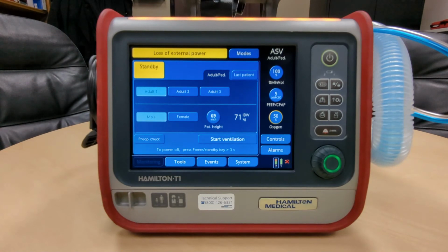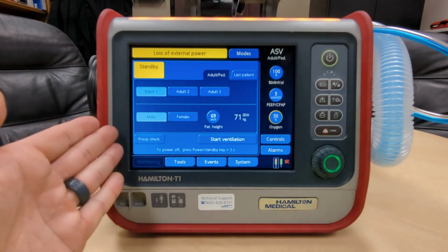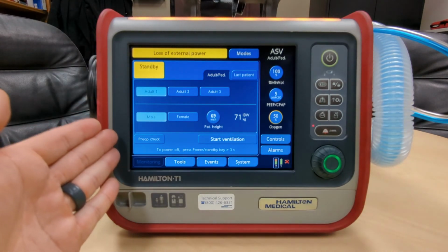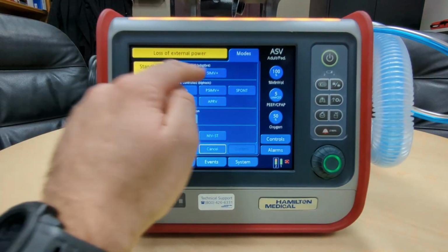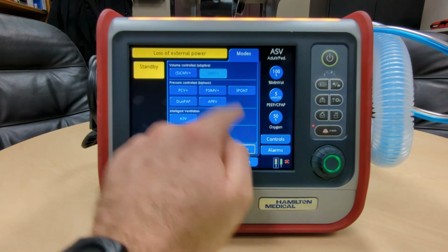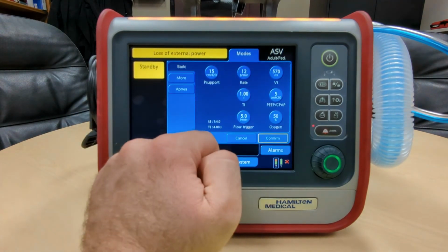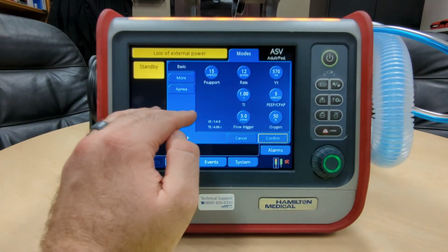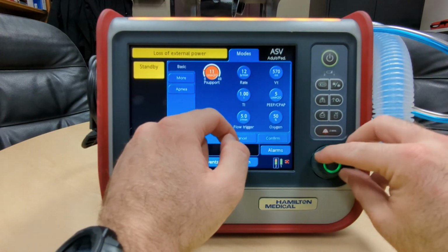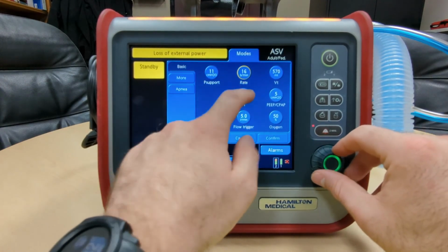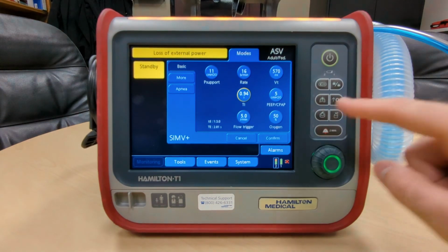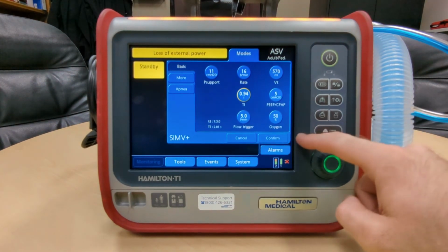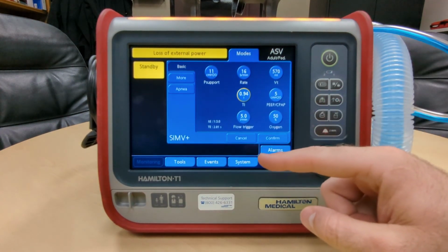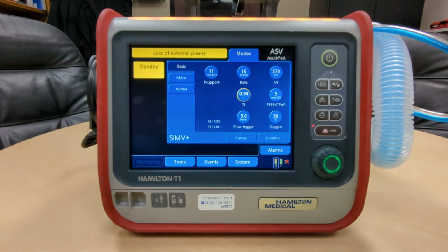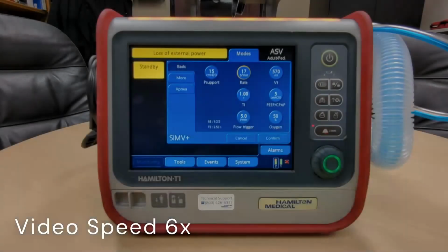One caveat worth mentioning is, when the ventilator boots in ASV mode and you decide to change the mode, for this example we'll use SIMV volume. So we do modes, SIMV volume, volume mode SIMV, confirm. This brings up the settings. You go in here and adjust this to whatever you want it to be. If you do not hit confirm, this will default back and go into ASV mode. Let's watch. I'll speed it up.